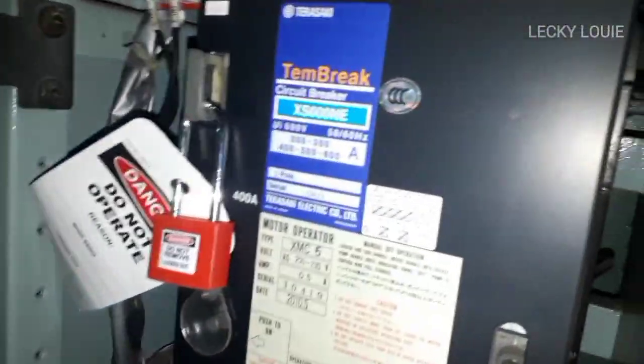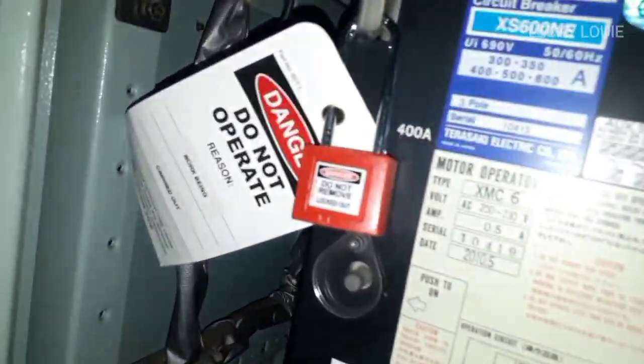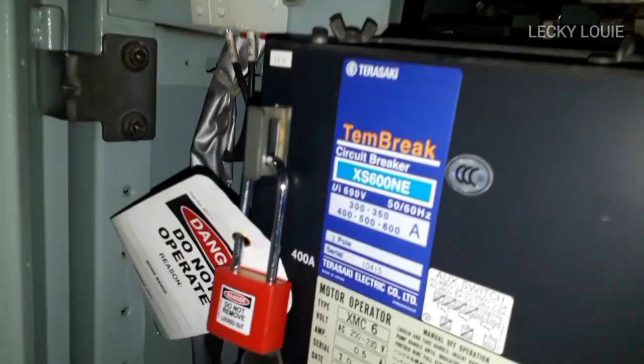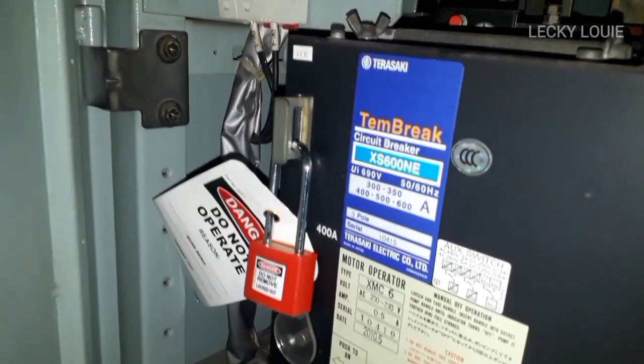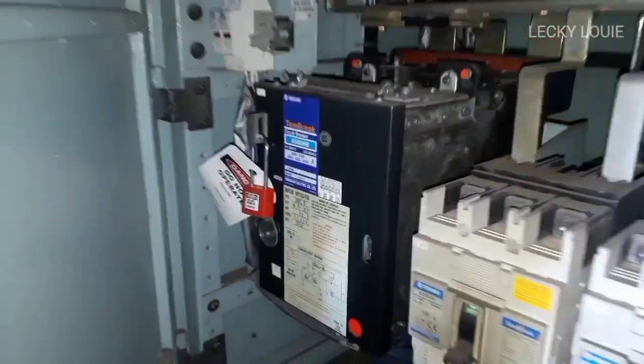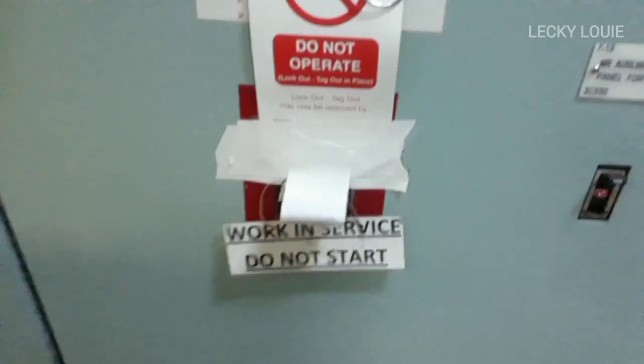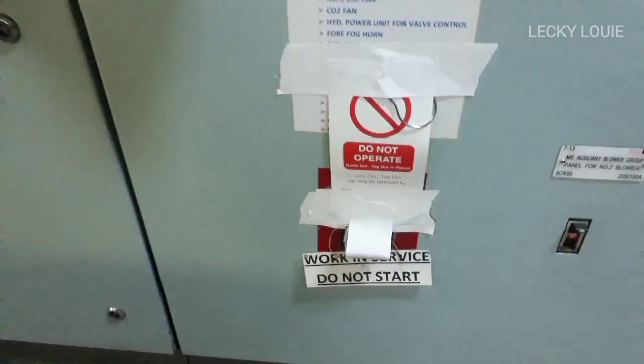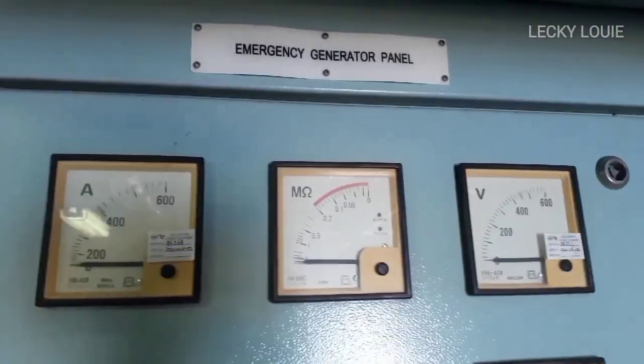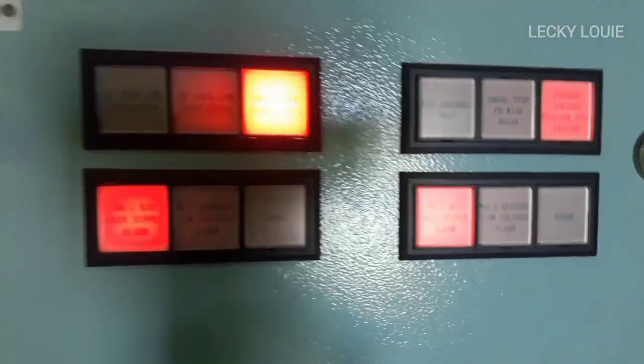Today we are going to replace the main circuit breaker of the emergency generator. But before we proceed, we need to isolate the tie breaker of the emergency switchboard and main switchboard. Also, the ESP breaker inside the engine control room needs to be isolated. And lastly, the emergency generator is put into manual mode and secured, so it will not start.